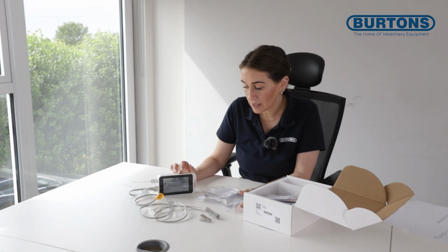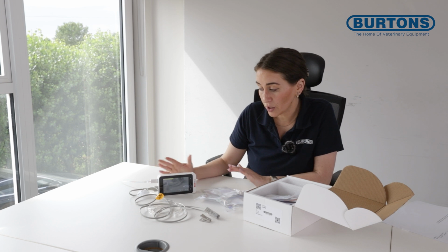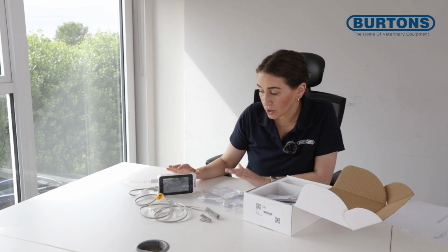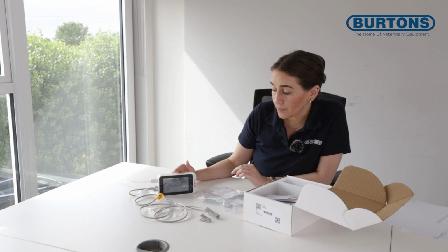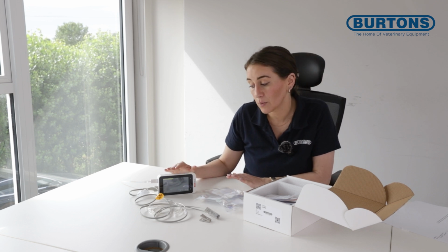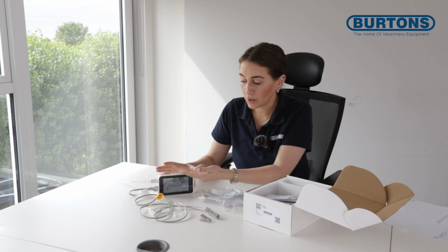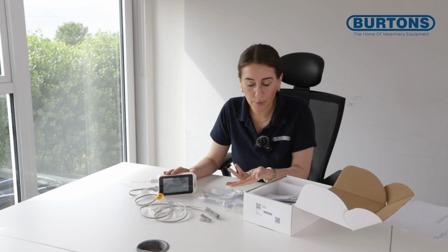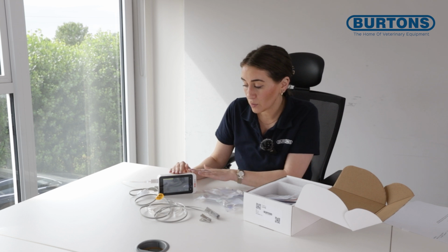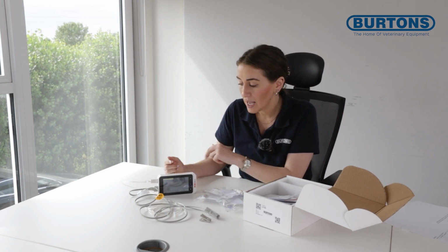So in terms of maintenance, the machine should run and operate as and when it's needed. It can have a yearly service to just make sure that the calibration is okay. And throughout its use, you might find that it will zero. So essentially the internal capnograph module needs to recalibrate over time, and that zeroing might look like a flat line of your respiratory rate or your capnograph, and it's just the machine recalibrating, and it will only be for a certain length of time and then will represent your patient's breath again. So that will do that every so often built into the system, and then obviously it can go for its yearly service.